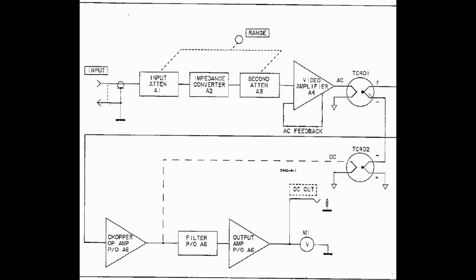What we do is once we get a voltage out of this, that voltage runs over to a chopper amp, comes out, and is fed back to the second thermocoupler to heat it, fed through the heating element here. Now this thermocoupler is reversed. They're not in series to produce higher voltage, they're actually differentially connected, so whatever this does offsets this the opposite direction.